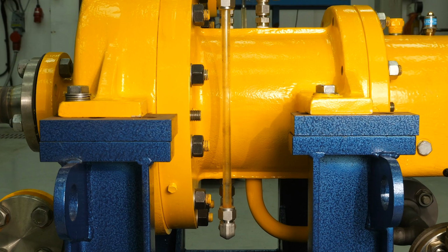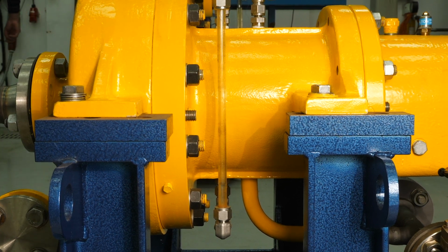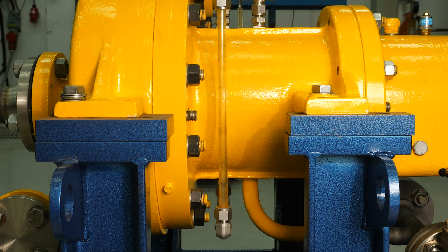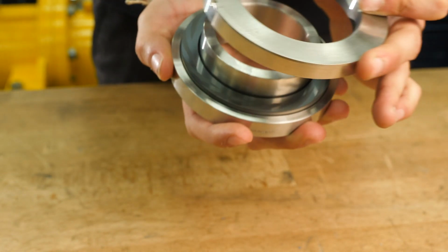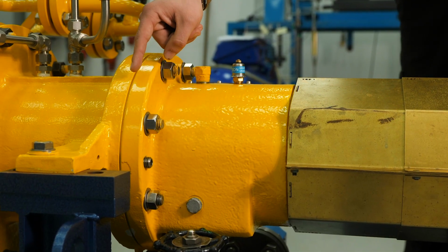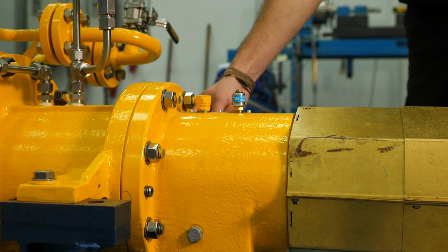The following sequence is a live demonstration of the HMD Kontro secondary containment system. This demonstration of secondary containment comprises an HMD Kontro general service pump. It has been modified to allow process liquid, which would normally flow into the rear of the pump, providing lubrication for the internal bearings and cooling for the magnetic coupling, to be diverted into the secondary pressure housing, where the outer part of the magnetic coupling is spinning in air. The pump has a dry-running mechanical seal positioned between the secondary pressure housing and the bearing housing. The bearing housing vents to atmosphere.